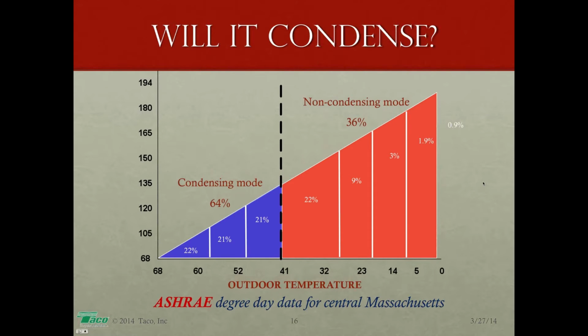And this comes from what Anthony provided here, ASHRAE degree day data for central Massachusetts. But this really does apply through most of the cold weather parts of the U.S. The outdoor temperature bottom end may change compared to northern Minnesota to central Massachusetts to Philadelphia to northern California. But the percentages are fairly consistent. If we take a look at this, you'll see the outdoor temperatures down below, and the percentages are the amount of time you spend in those temperature ranges.